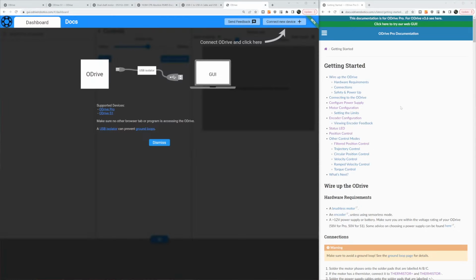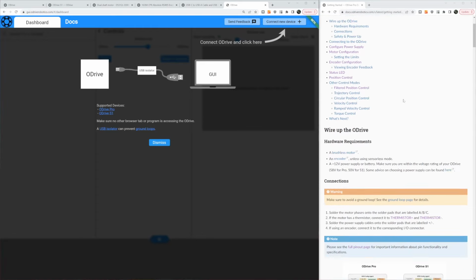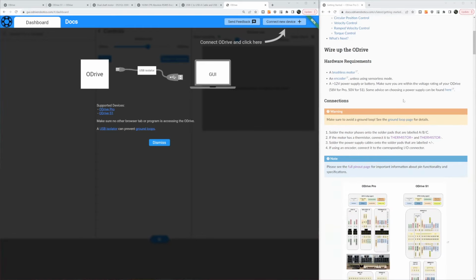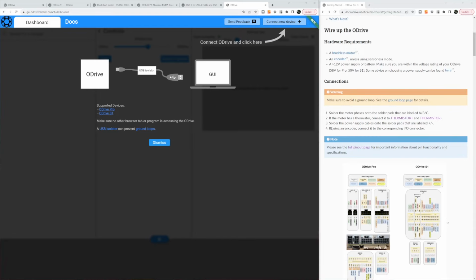Alright, so the first step is to wire up the hardware. I've already prepared this, but just quickly, you want to wire in the motor phases, the motor thermistor, the power input, and anything you have on the logic side, such as the encoder or any other input sources you may have. It's very important to make sure everything is tightened down and give it a tug test to make sure nothing's coming loose. I also have the motor bolted down here, so it's not going anywhere.